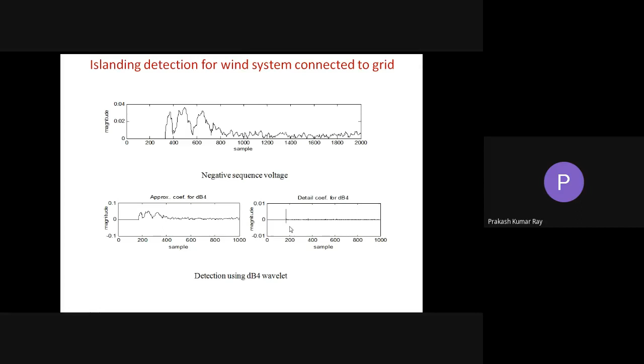So this is an islanding event. You can see suddenly, near 350 or 370, the magnitude is increasing because of the islanding event, and this is being detected by the wavelet transform. We have used the Daubechies 4 wavelet as the mother wavelet. At around the same point, the wavelet detects a change in magnitude in the system, meaning there is a disturbance like islanding in the system.